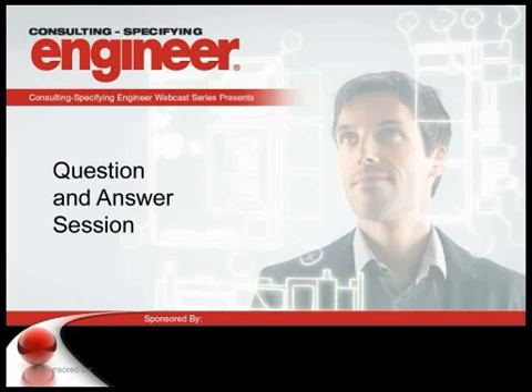So by the code, do you not have to consider utility and generator when overlapping neutrals? Jim? I was hoping you were going to say Dean, but I think that same question has been asked 3 times now, and that's an open debate.